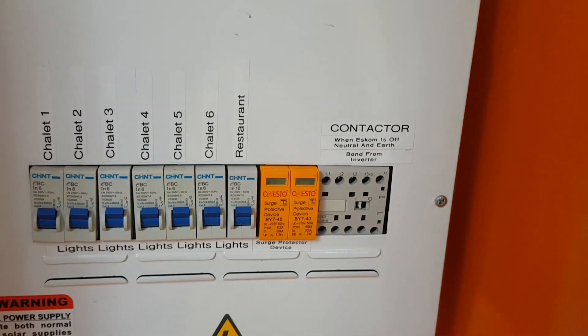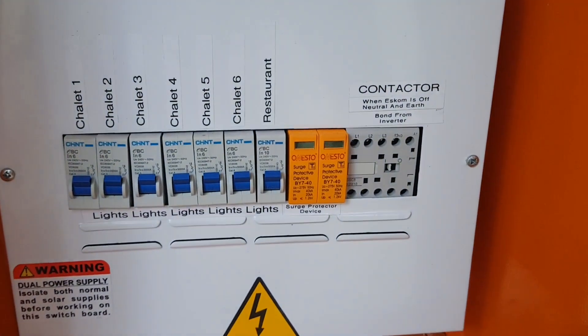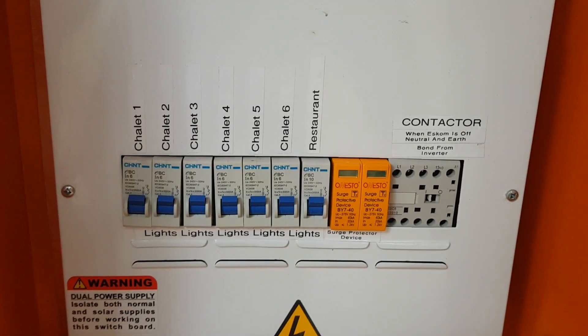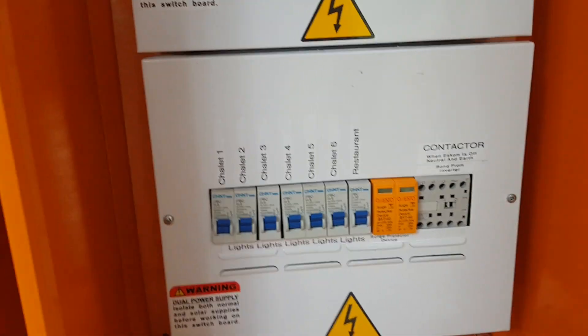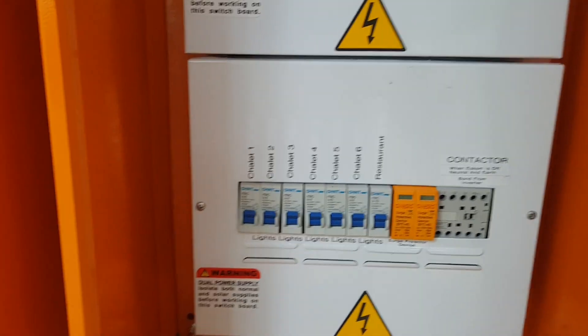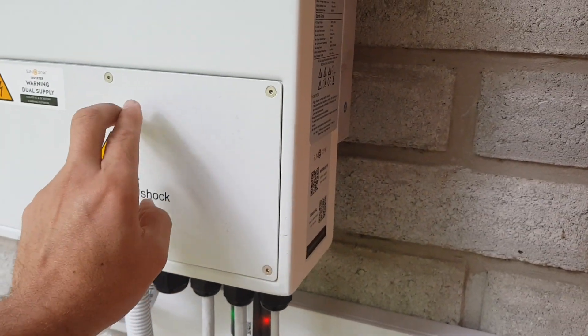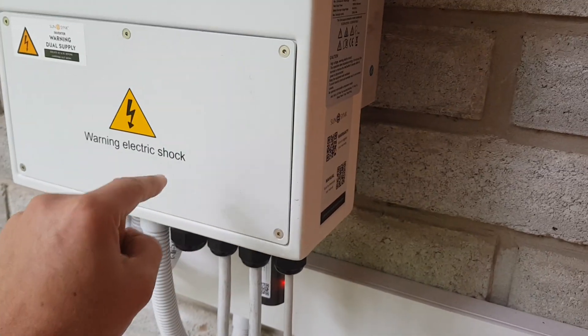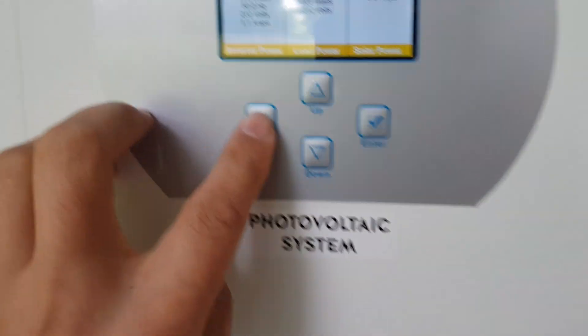We have to use this contactor with Sunsynk inverters because they do not do earth-neutral bonding inside the inverter itself. What I showed previously on the inside of the inverter is the connection where we run the signal cable or remote cable to switch that relay from the inverter's live and neutral port, which is meant for exactly that purpose.